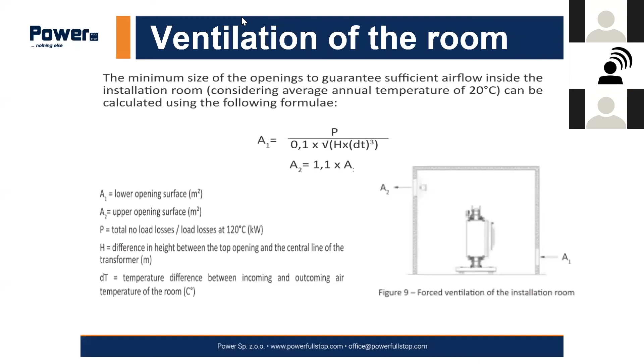I'm just accelerating because I saw we do not have so much time. So, forced ventilation is also something we can supply. I have just one indication for you: be careful when you are installing air conditioning inside the room where you have the transformer. The ventilation from the conditioner cannot blow directly on the transformer. Otherwise, what happens? You are creating a cold point on the transformer, and there could be some condensation problem on this transformer. So you could even damage it. Never blow the fresh air directly onto the transformer.